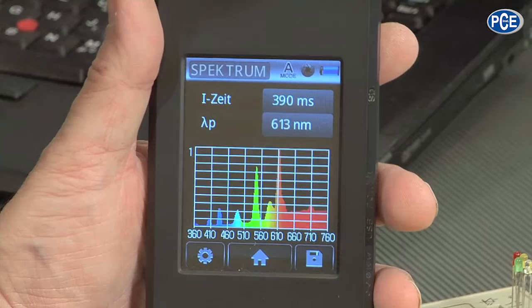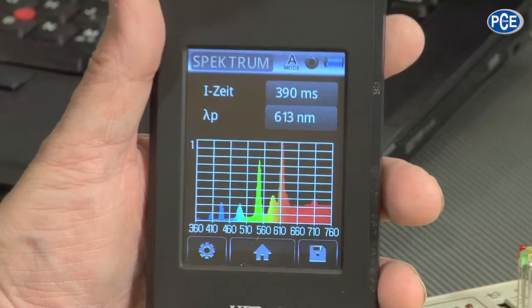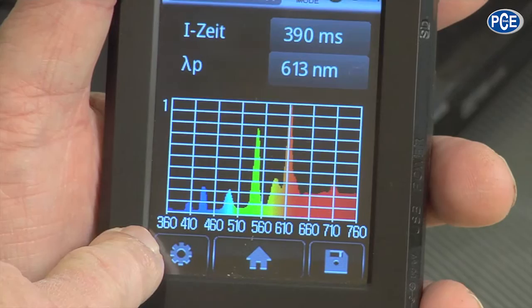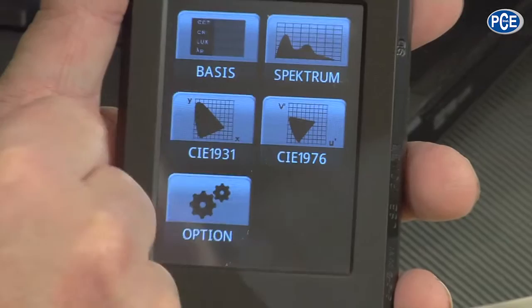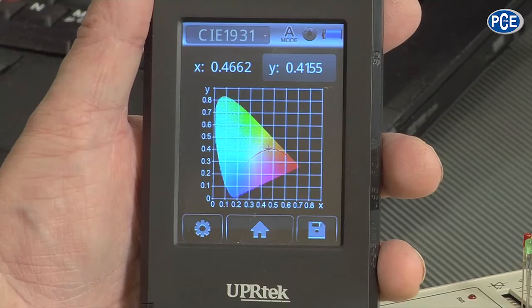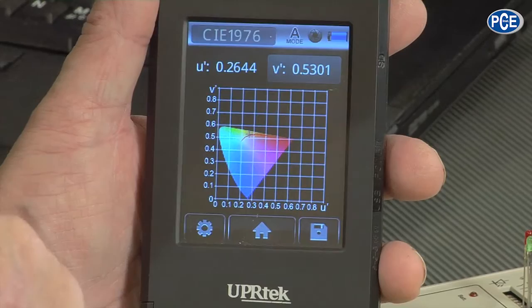The spectrum display goes from the left at 360 nanometers to the right up to 760 nanometers. You can see exactly there are a few peaks in it — it is distorted here in the studio because we have a lot of lighting. I can also have it shown in color spaces, for example the CIE 1931, where I can see how it is assessed, or the CIE 1976. All that I have in here I can have as a table for a spreadsheet calculation.